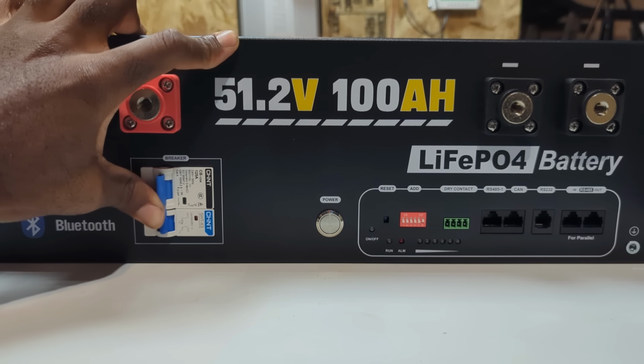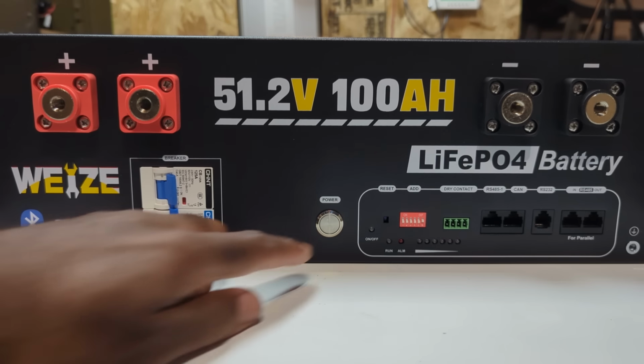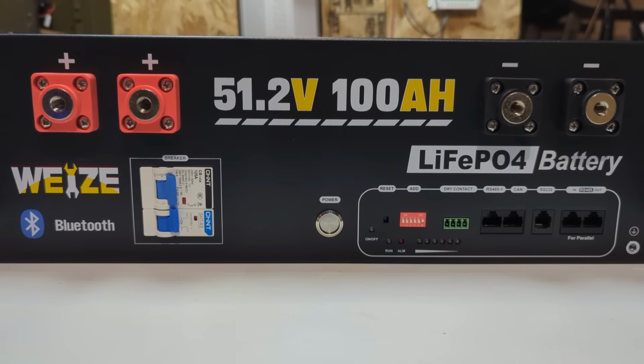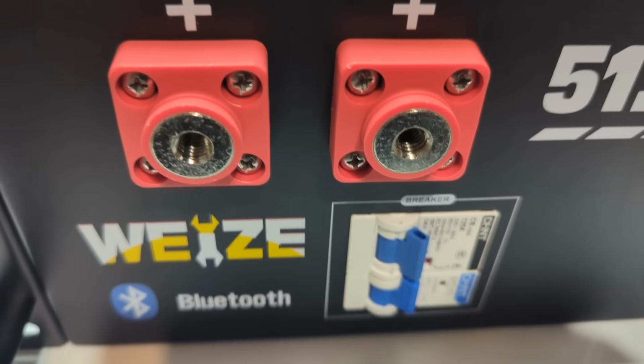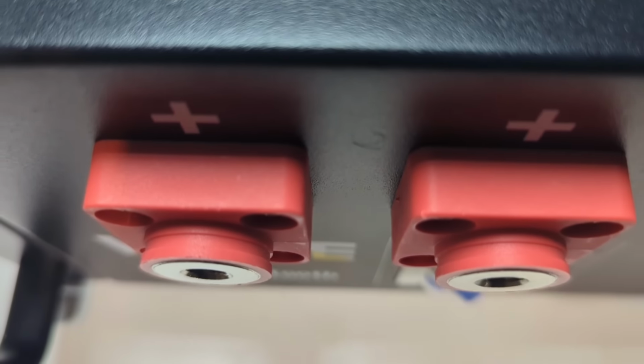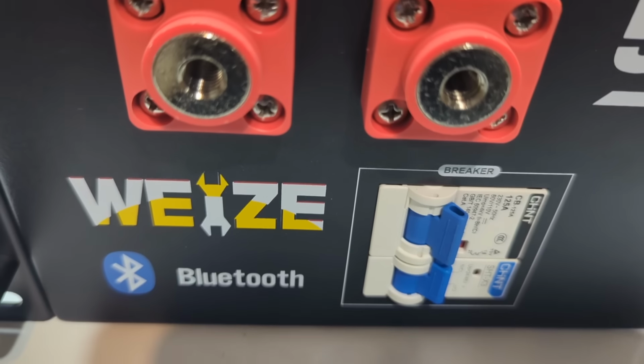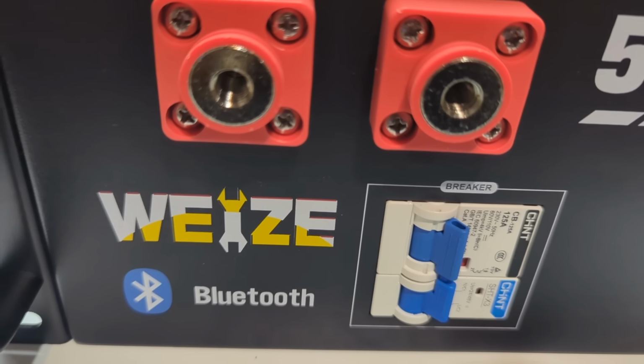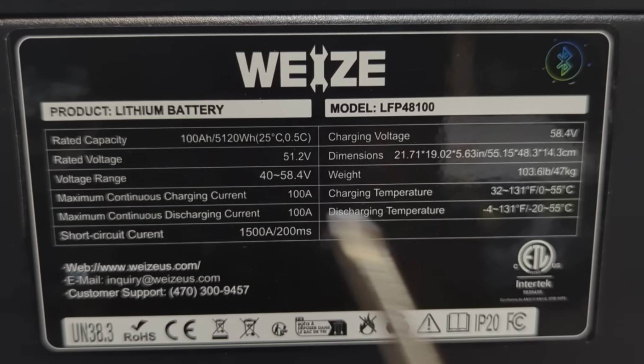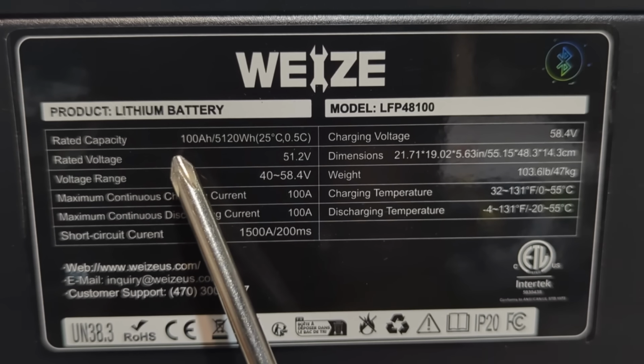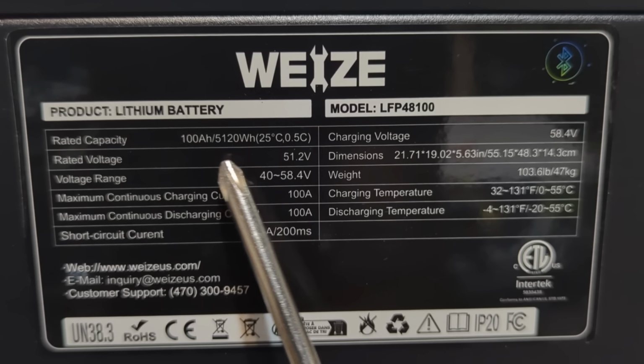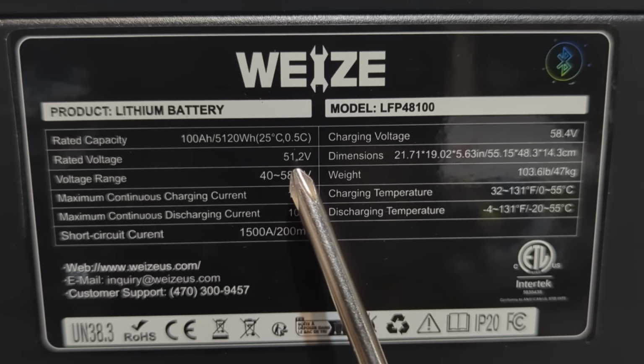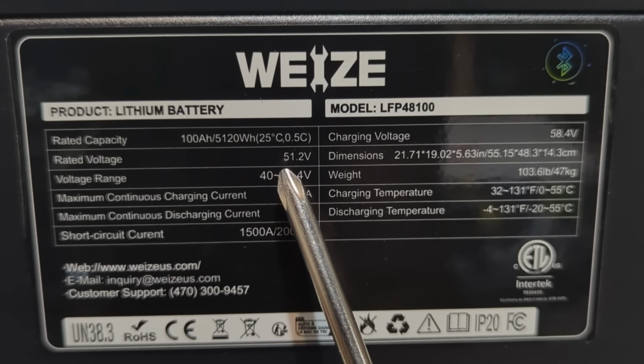Let's switch on the DC breaker and press the power button. I wanted to confirm everything was working properly before taking a look inside the unit. I like how the battery terminal fasteners are not poking out. There's no way they can come in contact with your wire lug. The specification label says 100 amp hour, total capacity 5120 watt hour. This battery was tested and verified at 77 degrees Fahrenheit at 50 amp.